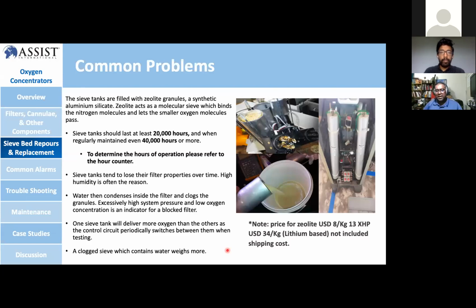And zeolite price is normally about $8 USD for 1 kilo. It has a code name of 13XHP. That's the normal zeolite that you use for 0 to 5 liter per minute oxygen concentrators, and you can use it up to 8 liter per minute types. The other one is USD $34 per kilo, lithium based, and these prices do not include shipping. The lithium type has a much longer lifespan, so that's the reason it's a bit expensive.